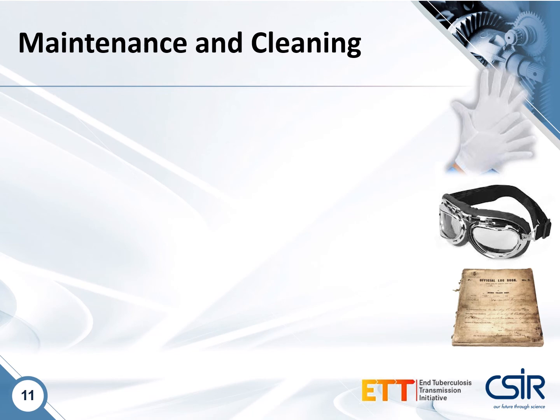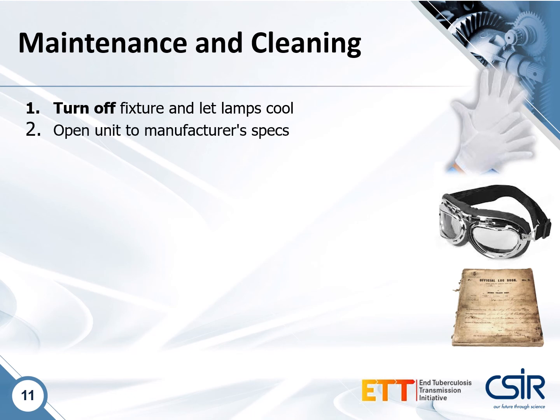The maintenance and cleaning of UVGI devices need not be technically difficult or onerous. Just make sure that you are aware of some cautionary notes in your procedures. Firstly, you need to turn off your fixtures to let the lamps and control gear cool. These can get quite warm, and you don't want to handle them in that state. You might harm yourself or the device. Then, once cooled down, open up the unit to the manufacturer's instructions. Some units do open much more easily than others. Some devices require a significant amount of disassembly to get into the unit to clean it. So this is something you just want to be aware of when you are specifying or procuring new systems. Make sure that the ones that you procure are easily maintainable.